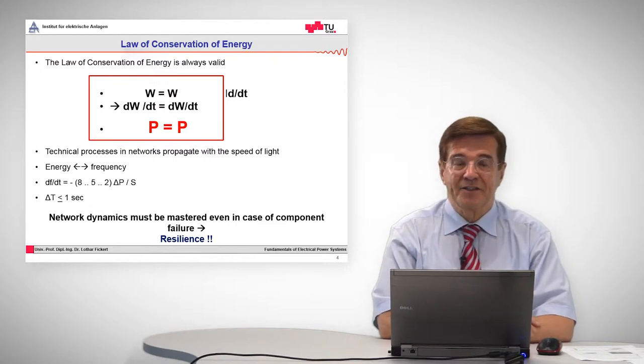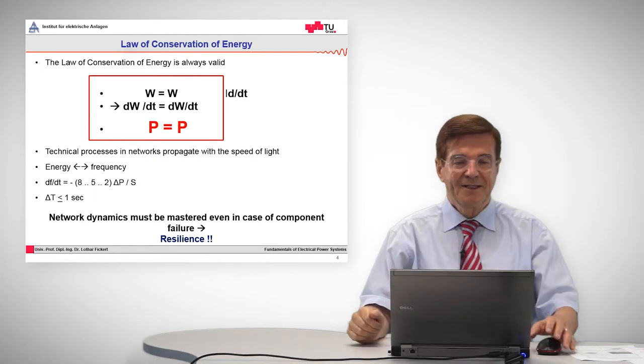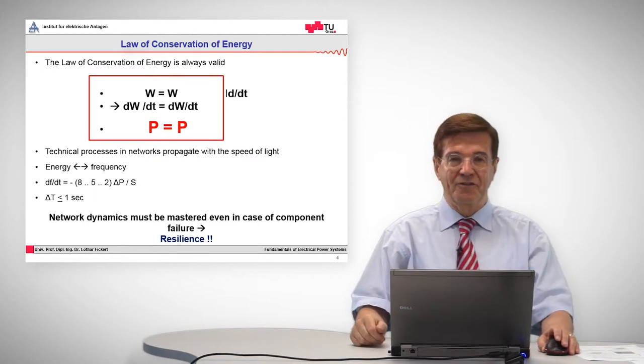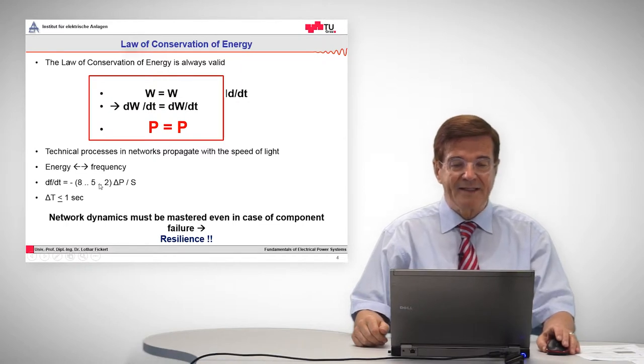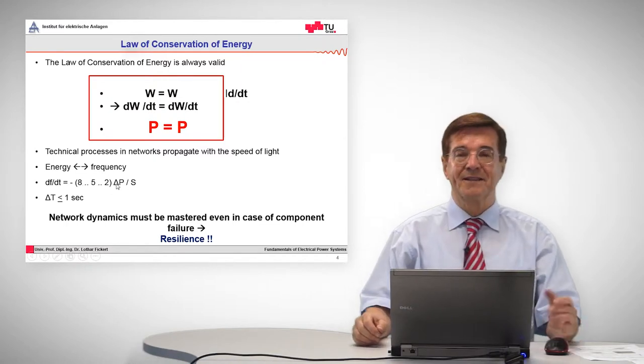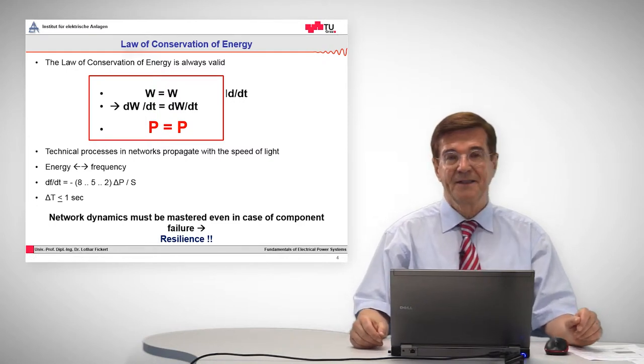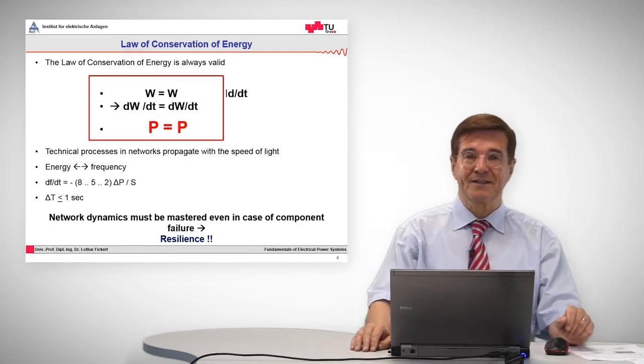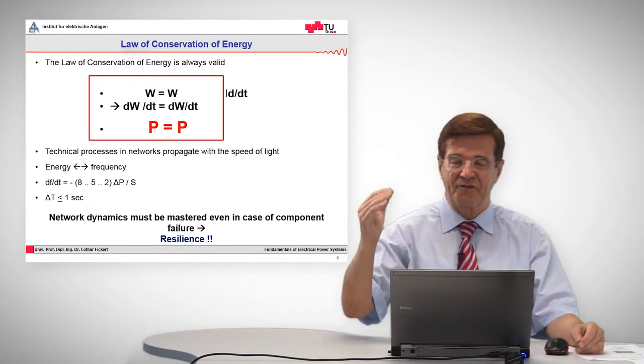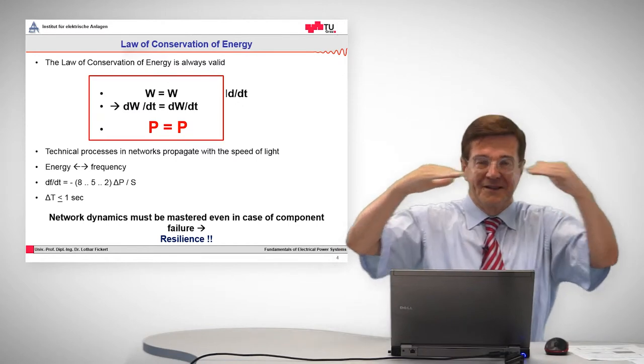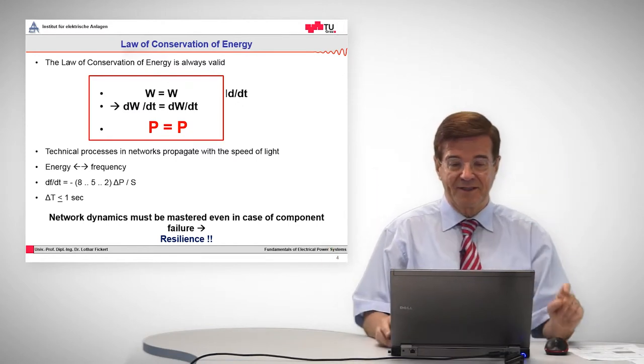When for example there is a loss of energy, a loss of power in a system, the frequency will go sharply down with the rate of change of frequency, which you can see here, which is minus eight times the deficit in per unit, and this comes out in Hertz per second. And since the regulators have to come up and cope with this rapid change of frequency in order to keep the frequency constant, they have only one second of time to do this.